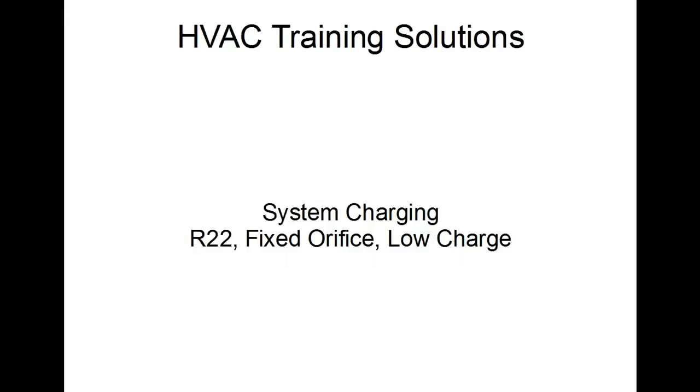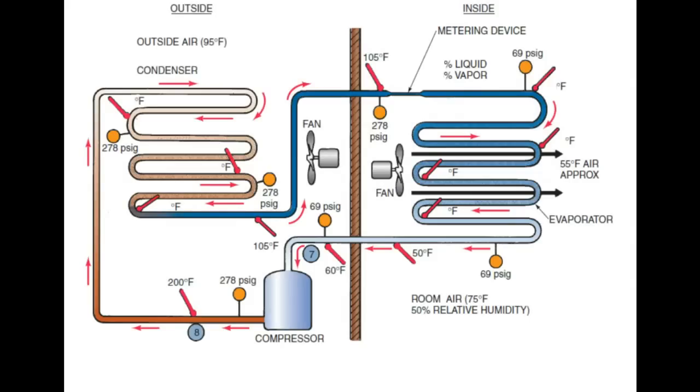System charging. Hey, let's take a look at an R22 system, fixed orifice and a low charge and see what's going on with this refrigerant and the refrigeration cycle. We're only going to look at the evaporator side at this point. For a quick review, this is our diagram from Module 3. And in a system that is properly charged, you do have a solid column of liquid refrigerant that enters the metering device. Remember, this is fixed orifice.